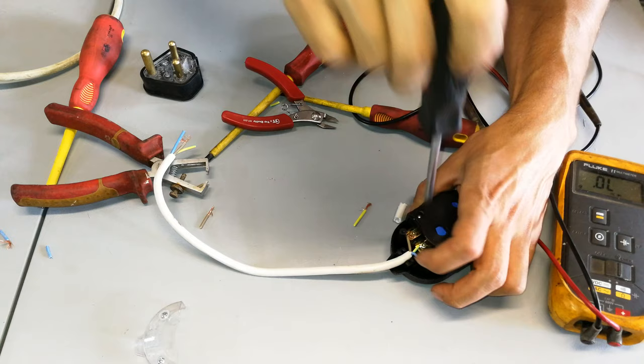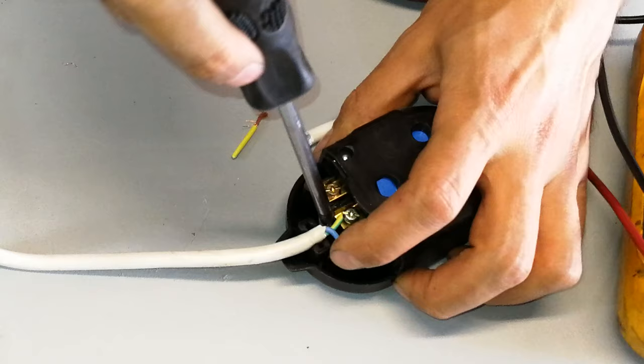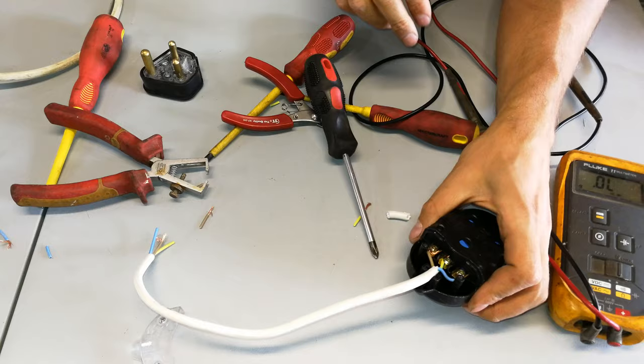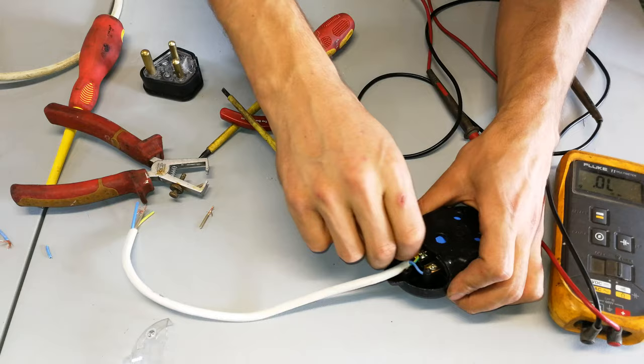And then I'm just going to tighten it. Now, very important is just hold it in place while you're tightening it. And if you could, try put it on the left-hand side so that when it tightens, it wants to rotate the wire. You see there, look what it did there. Made a bit of a mess of it. And this is the only problem with couplers that don't have plates that come together. You see what it did there.